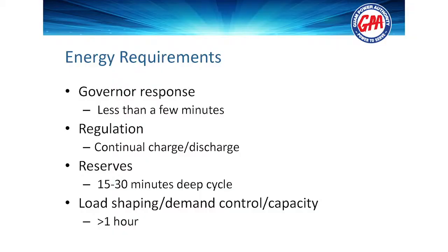So this is another application where it may actually be good for a hybrid system. The system I was telling you about in Alaska, that's about a 20 megawatt system, they started out with a 2 megawatt battery that was designed for deep discharge. But because of the variability of the wind, their battery life started degrading so fast that they've decided to put in flywheels to take care of the regulation and then save the batteries for deep discharge. The next one is load shaping and demand control, which I think John Benavente talked about earlier. It's trying to shift your energy to a cheaper period of time. Okay, next.